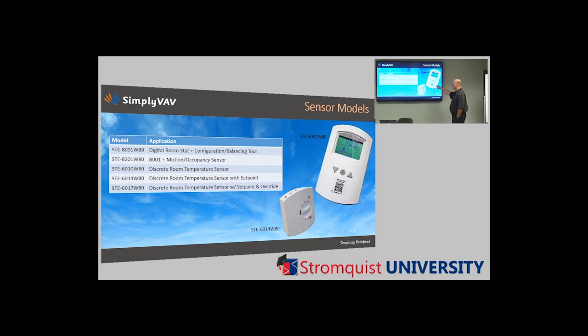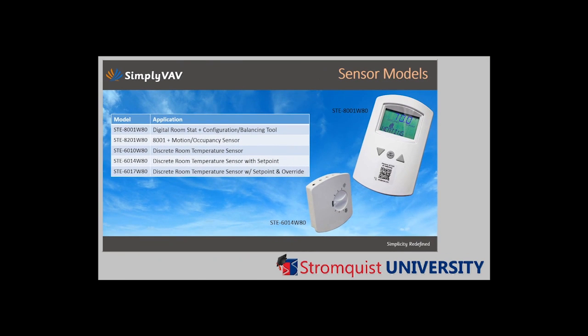On the sensor side, the STE8001 is your software configuration tool. This is the device that you will use to start up, commission, balance, and install the system. There are, however, a couple of other flavors of discrete, smaller thermistor-based occupancy or temperature sensors that you can use. They're available with or without set point, with or without override options. If the job dictates that you have to go this route because of cost, one thing to bear in mind is you will need at least one STE8001 simply to use as a configuration tool at the startup, and then when you're done, you can go ahead and take that off and plug the STE6000 or the smaller temperature sensor back in.